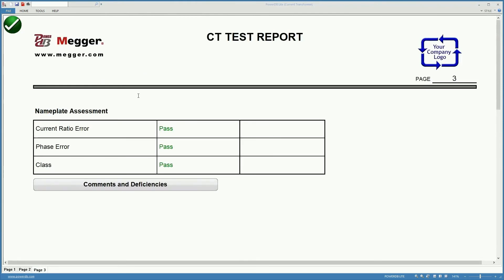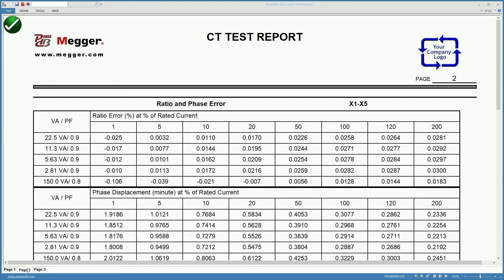And down here we have a nameplate assessment. Current ratio error is a pass, phase error is a pass, and the class is a pass.